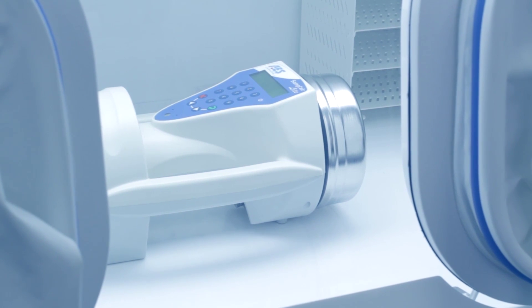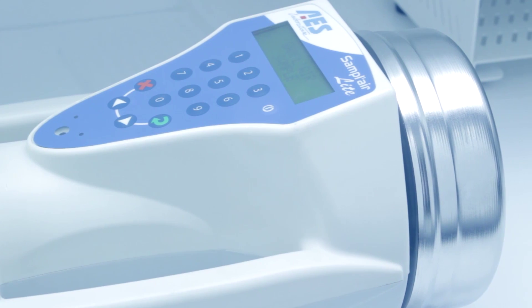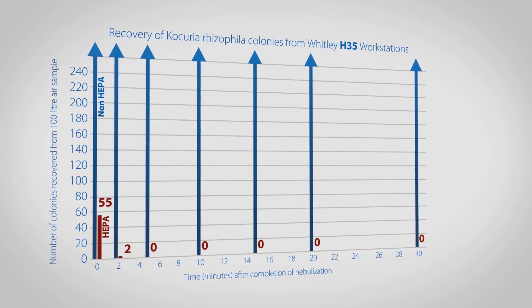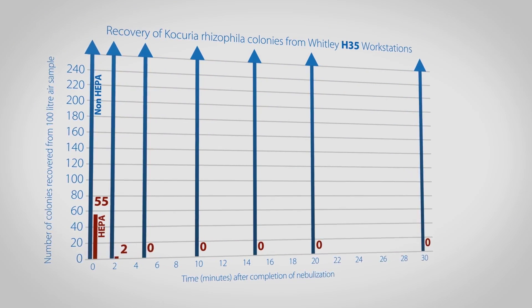Bacteria remaining within the atmosphere were then collected at intervals using an air sampler. In a HEPA workstation, within two minutes after completion of nebulization, the viable bacterial count was reduced more than 100-fold in comparison with the equivalent non-HEPA model, and within five minutes the organism was no longer recovered.